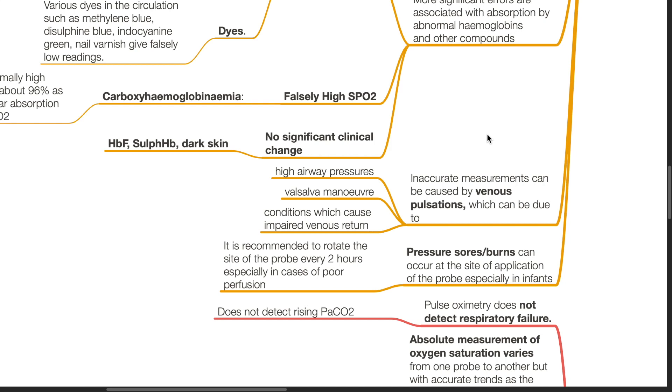Pressure sores and burns can occur at the site of application of the SpO2 probe, especially in infants and at body parts of poor perfusion. It is recommended to rotate the site of the probe every 2 hours.